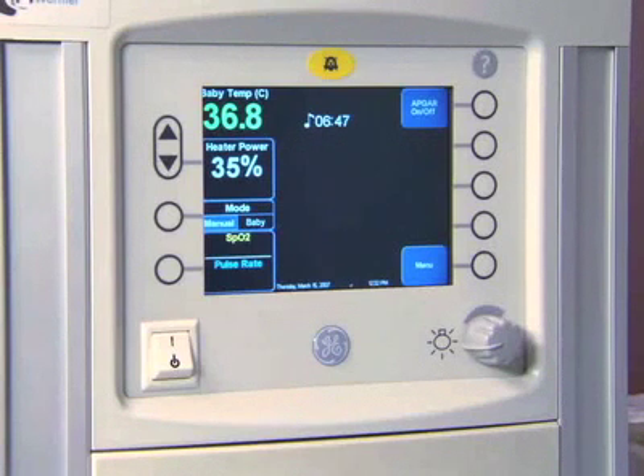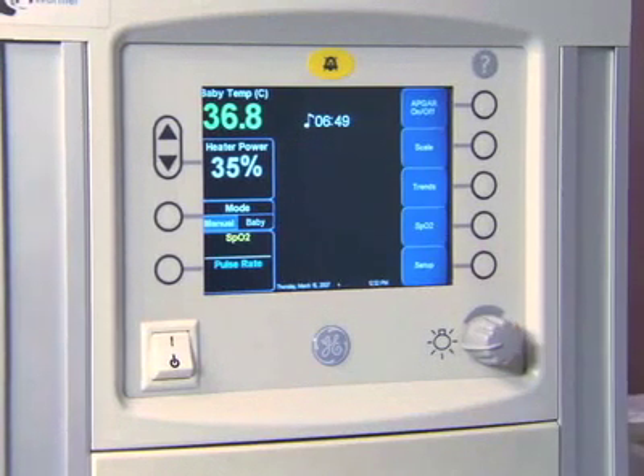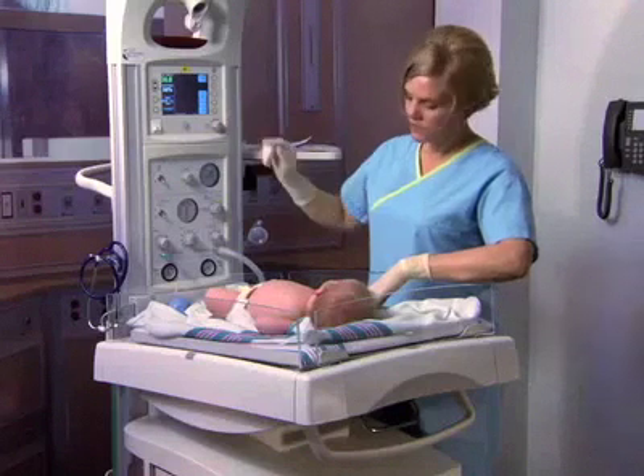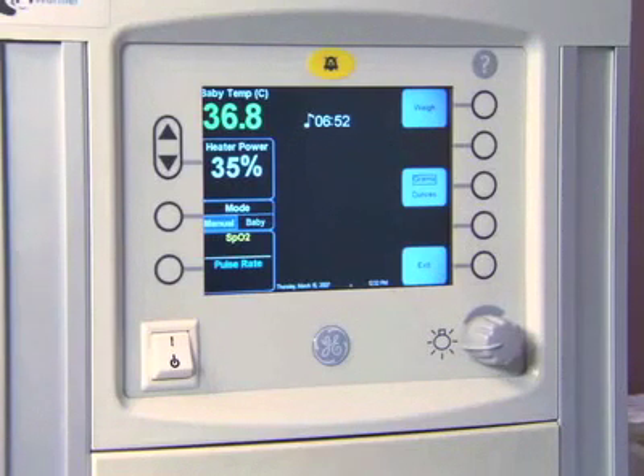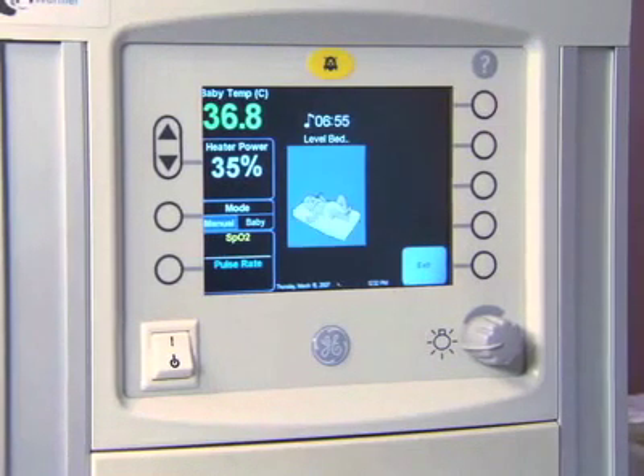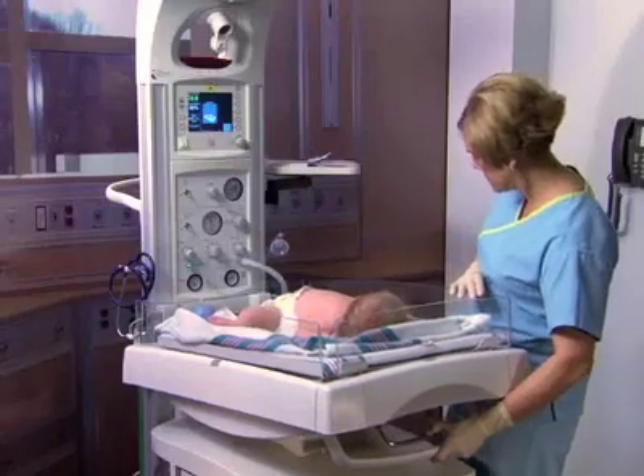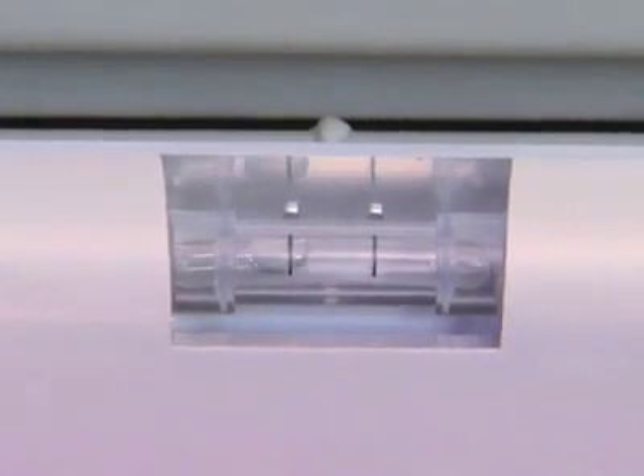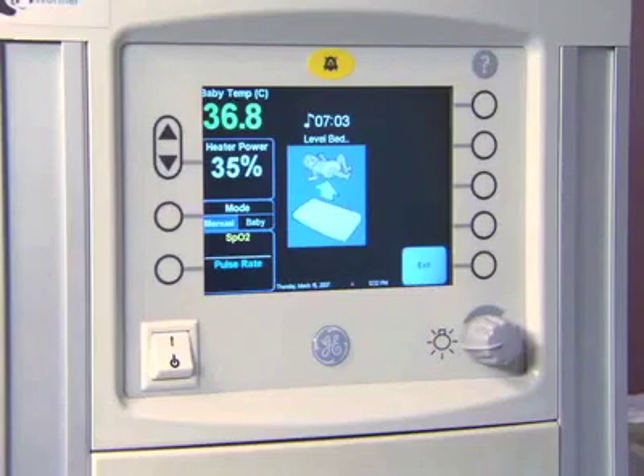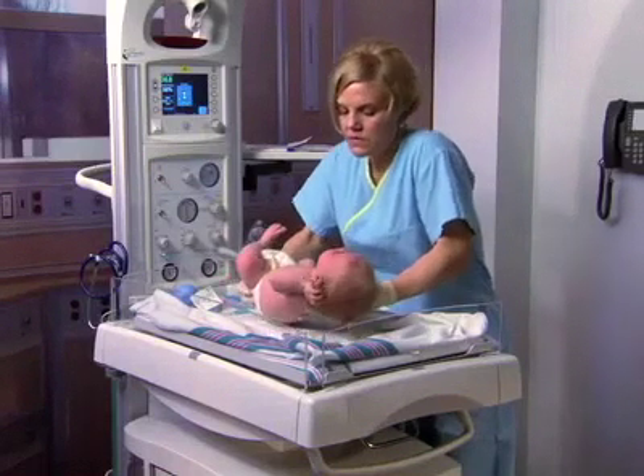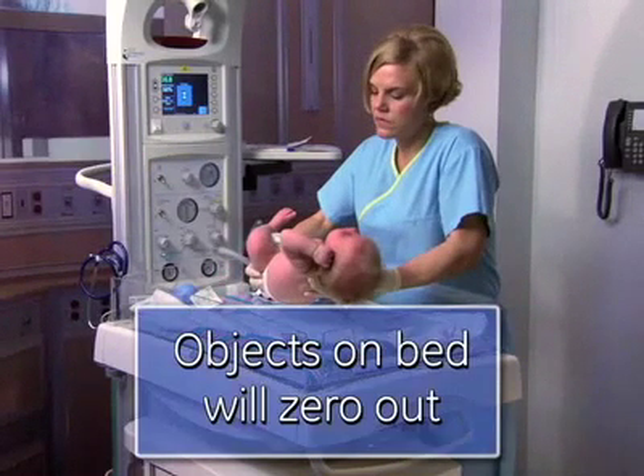To begin, press the menu key, then press Scale. If the scale is not connected, no icon will appear. To weigh the baby, press Weigh. You will first be prompted to check the side level to ensure the bed is level during weighing. Next, you will be prompted to lift the baby. This allows the scale to zero. If an object such as a laryngoscope is on the bed, it will zero out when the baby is lifted.